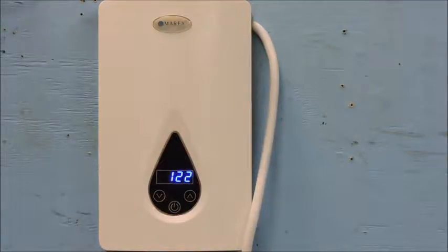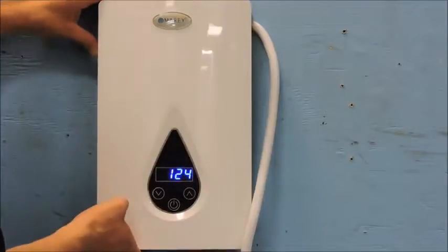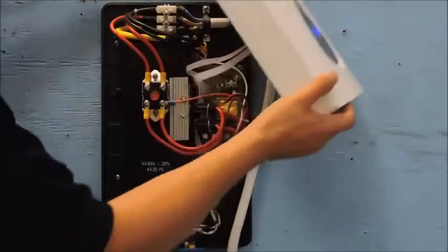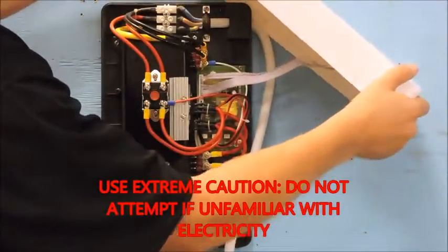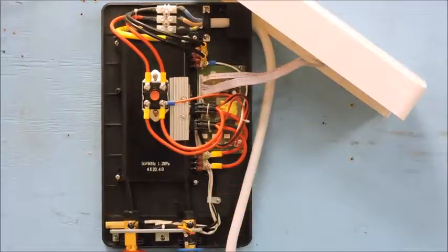If the unit is heating inadequately or not to spec, then we'll need to confirm the power through the unit. This should be done with extreme caution. Only attempt this step if you have a safe working knowledge of electricity. While the unit is running, remove the front cover and place it on the upper right corner, leaving the ribbon cable in place. First, we will confirm power being supplied to the unit.